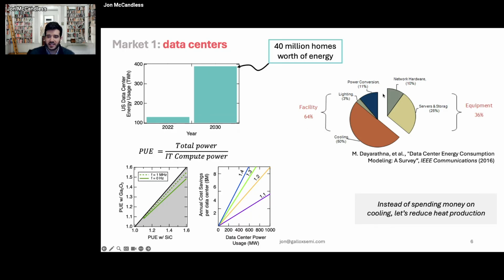Looking at a breakdown of how energy is spent within a data center, 36% goes to the equipment and 64% to the facility. The dominant contributor to facility energy consumption is cooling, about 50%, then power electronics losses at 11%, and lighting.